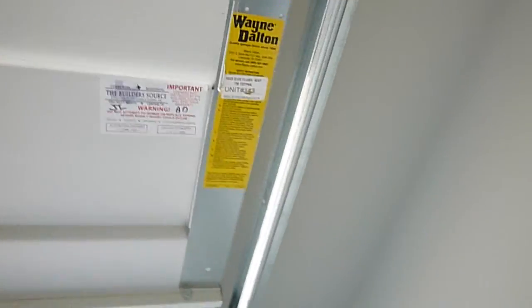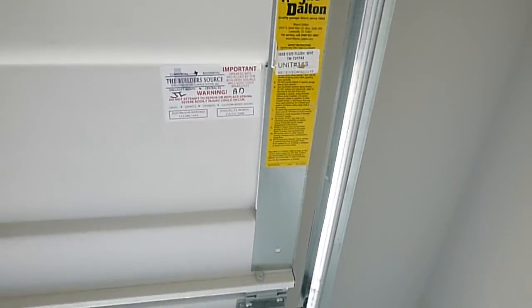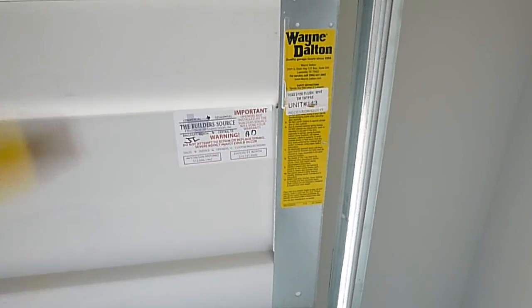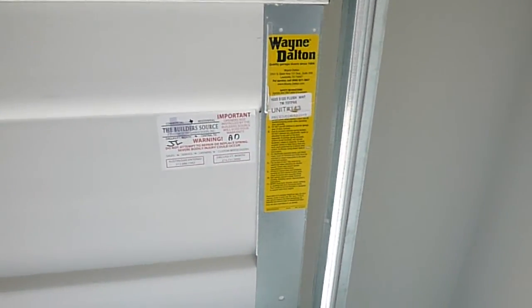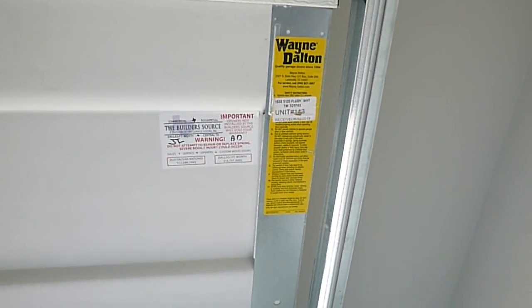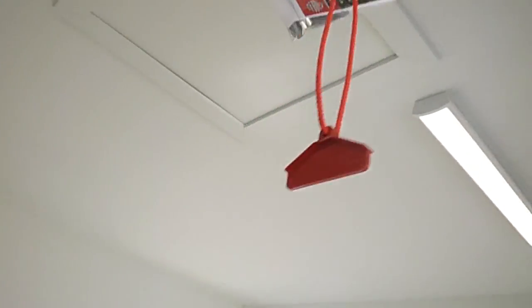Now, this is also the warning notice for the door, the safety warning notice about entrapment, and they put a sticker over that, so it's not legible. There also should be a handle on the interior side of this door, which there's not. This is the emergency control handle.